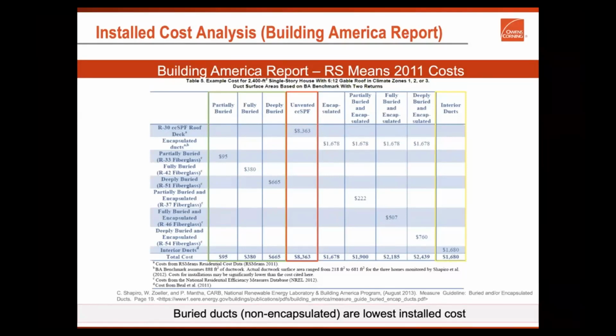Now, are you looking at a 2x4 truss like that? Would your recommendation be to have 3.5 inches of insulation and then run it across the top? I saw in the other picture, ideally you're running it parallel to the joist and you can run it right on the drywall, but where you have to run perpendicular to the bottom chord of the truss, you want that duct running laser straight. So you want 3.5 inches of fiberglass underneath it. Is that right? Yeah, correct.